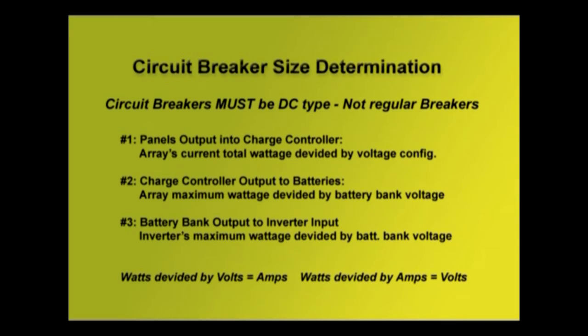So in number 1, our panel's output into the charge controller. We're going to put a circuit breaker there. And what you do is take the array's total wattage, you know the total wattage, maybe a half kilowatt, a kilowatt, 2 kilowatts, and divide it by the voltage output. That's the configuration, the way you've put those panels together to run that higher voltage coming in, or maybe it's whatever the voltage is. Divide that voltage into the total wattage of the panel, and that's going to be the maximum amount of current that you're going to see coming from this array. And then we're going to go with 1.5 times whatever that amperage is for that safety elbow room.